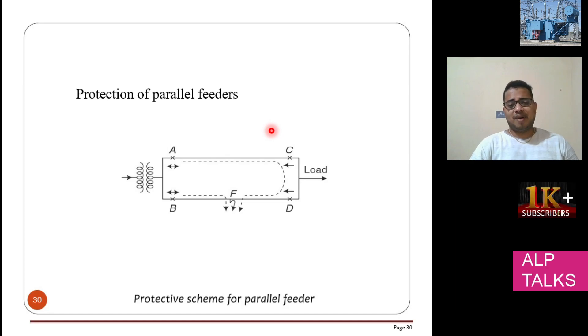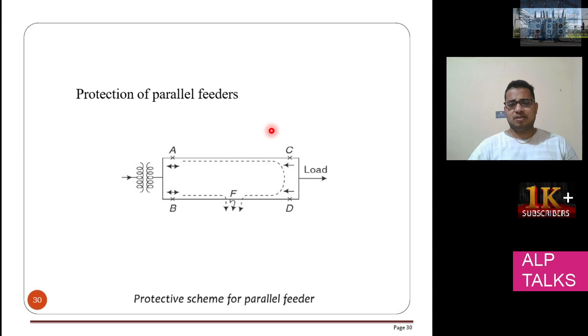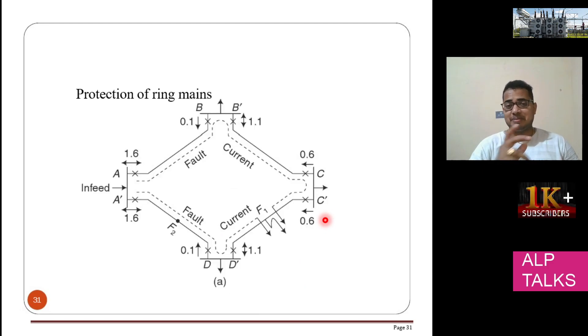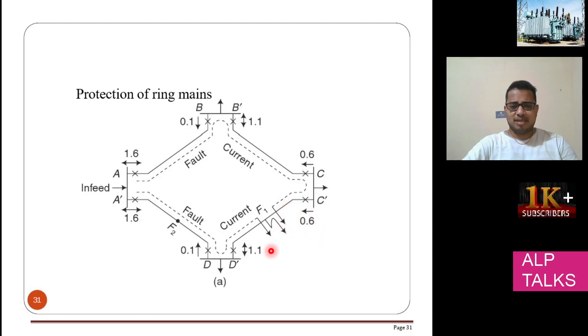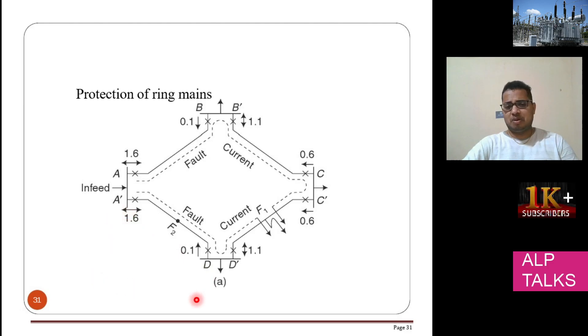For the protection of parallel feeders, where two feeders are present, when a fault occurs at F, both relays B and D will operate. Sometimes a ring main unit is also used. For the ring main, if fault F1 occurs, relays C' and D' operate. If fault F2 occurs, relays D and A' operate.